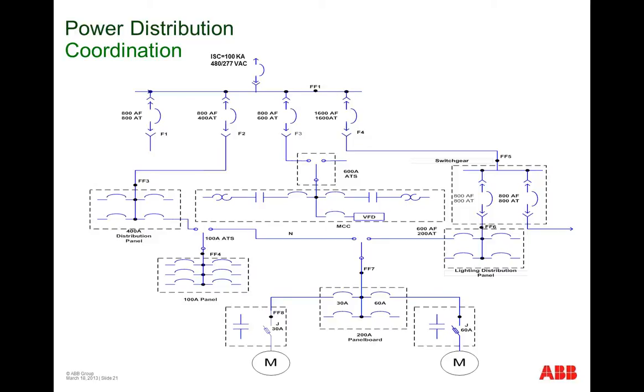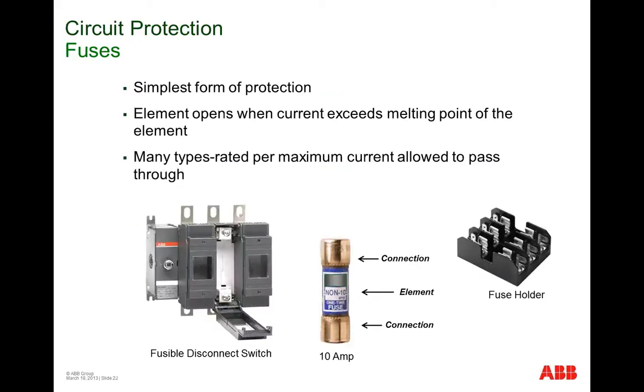Shown here is a one-line diagram depicting power distribution in a typical factory. But what I'd like you to notice is how it resembles an organization chart of levels of management in an organization. The concept is similar in that decisions are pushed down to the lowest level. A circuit breaker can trip to protect one motor that may be overloaded, isolating just that motor, and hence not taking down the operation of the whole facility by tripping the main incoming circuit breaker at the very top of the circuit. Engineers must size and select short circuit protection at all levels to coordinate their systems so that electrical faults or short circuits are cleared at the very lowest level. This helps to maximize the productivity of the remainder of the facility.